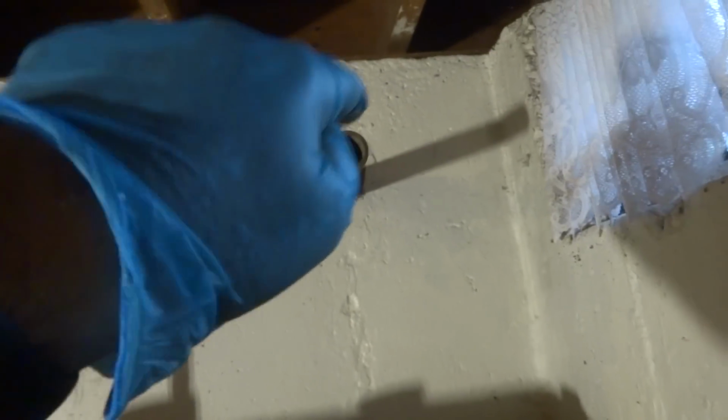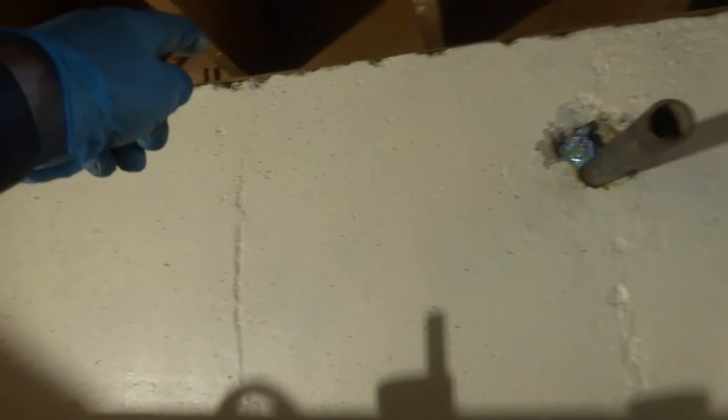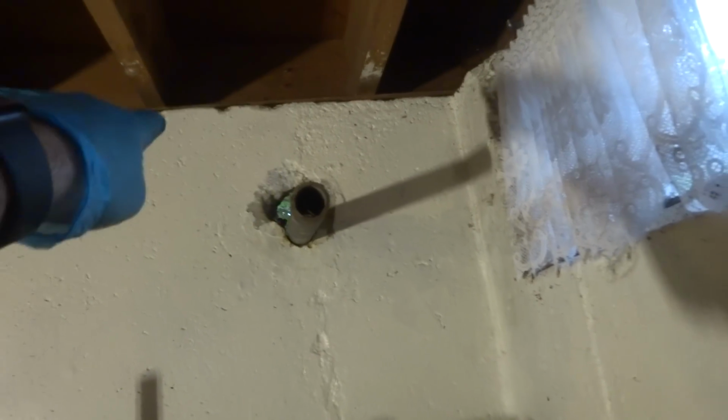And all I gotta do is pipe this off. This is gonna be the fill, it's gonna go up and on the bottom, and the vent's gonna come off the top, swing joint and out, and then the swing joint out top. This goes down and out that way. So when they fill it, the arm goes that way. You don't want this arm to hit the fill. So I don't know if you can see that.